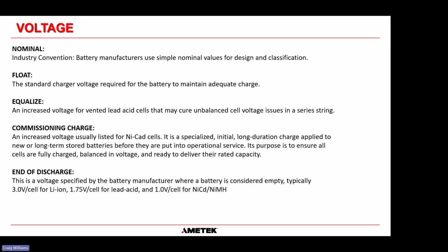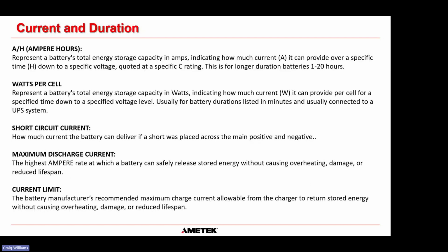The last voltage we'll discuss is the end of discharge voltage, specified by a battery manufacturer as the point when a battery is considered empty. Typically for lithium ion it's 3 volts, for lead acid it's 1.75 volts, and for NiCad it's 1 volt. These vary slightly depending on what you're trying to get out of the battery. That's all the voltages we may mention throughout this presentation.